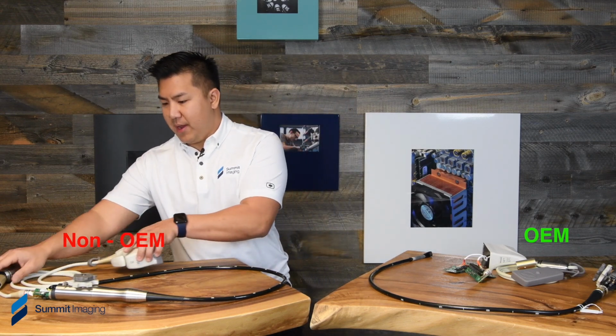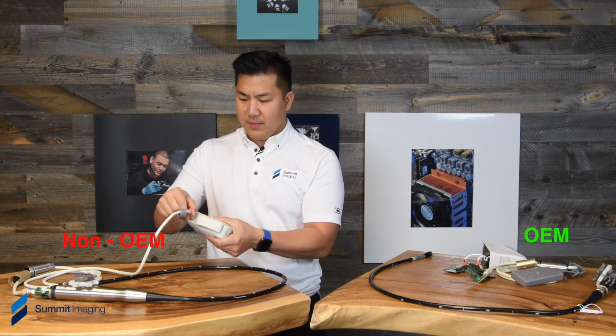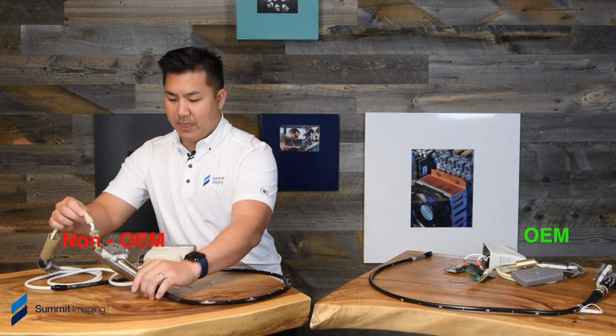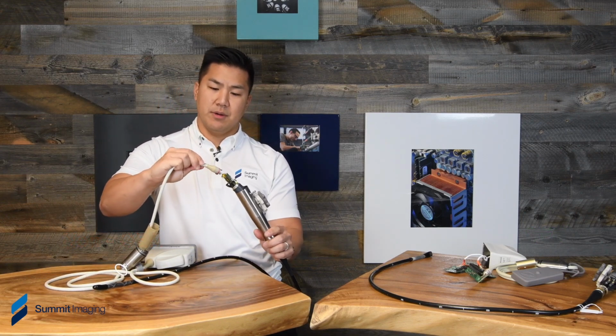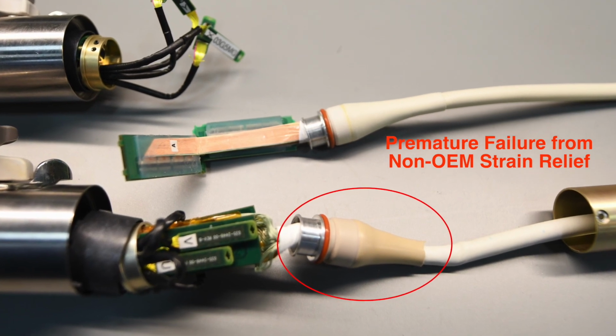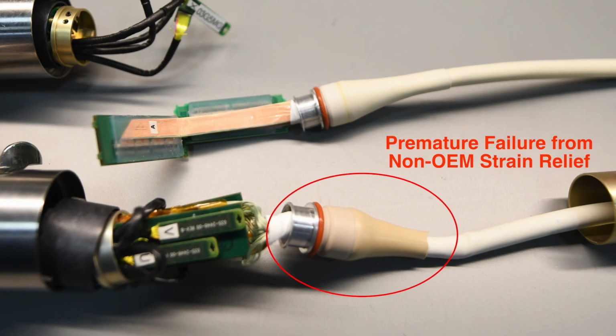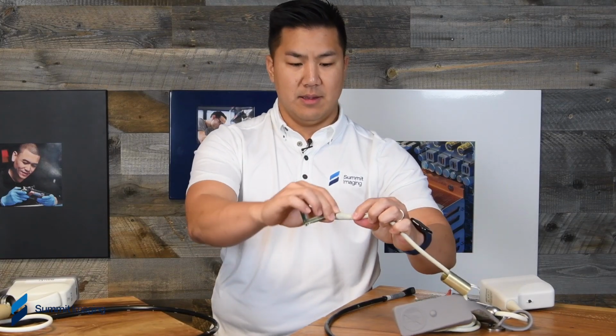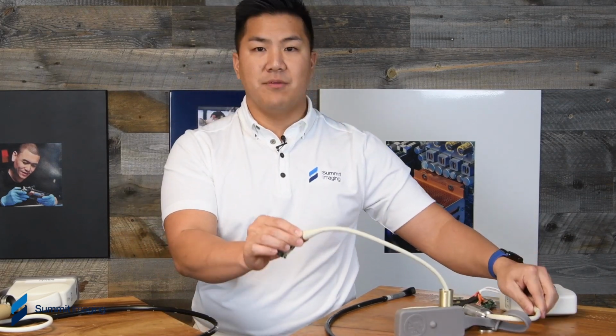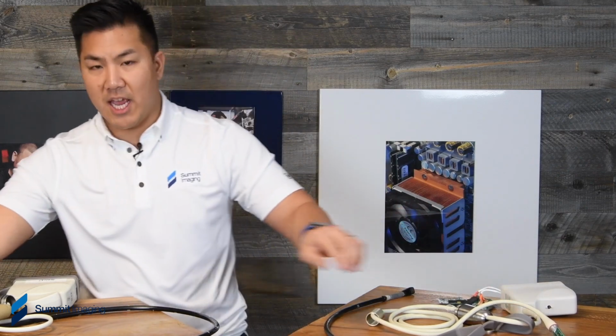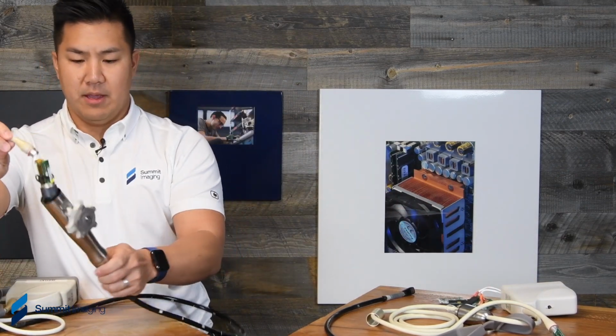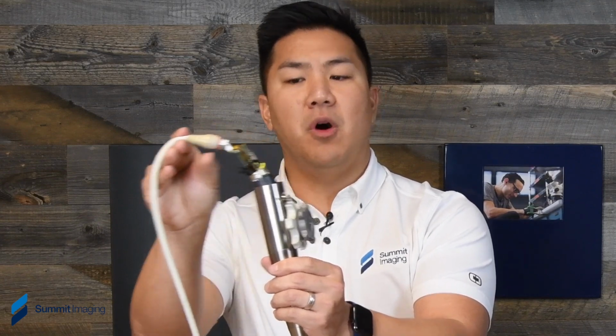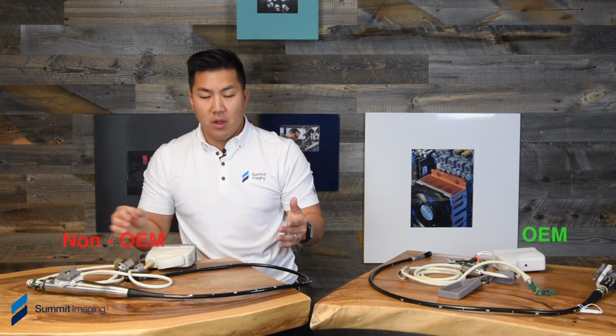So first and foremost, we have a strain relief, and you can see, and we're going to do a close-up of this, that this strain relief is already torn. And this is actually a premature failure. It's discoloring, and when you actually assess the material and compare it to what an OEM strain relief looks like, it's definitely not the same. And so by virtue of having different physical properties and it being damaged so prematurely, I can actually now change where the cable is bending, and now because the strain relief is torn and shortened, it actually changes the pressure point and increases the pressure and the strain of all the micro lines that are inside the cable. How is that a problem?